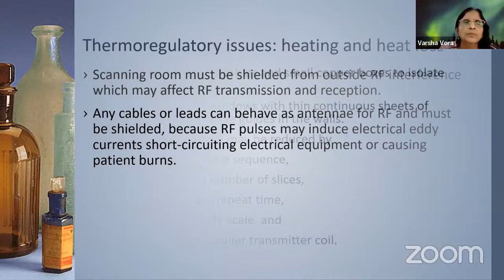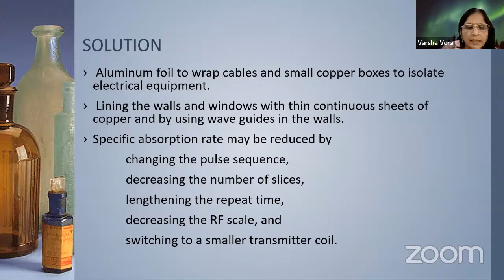Solution: aluminum foil to wrap cables and small copper boxes to isolate electric equipment. Lining the walls and window with thin continuous sheet of copper and by using waveguides in the wall. Specific absorption may be reduced by changing the pulse sequence, decreasing the number of slices, lengthening the repeat time, decreasing the RF scale, and switching to a smaller transmitter coil.